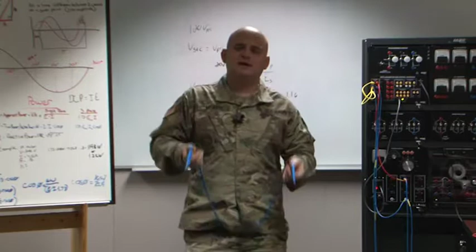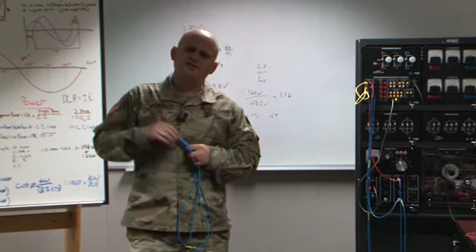For instance, if I have one transformer rated at 100 kVA, and I put it in parallel with another 100 kVA transformer, and another 100 kVA transformer, so three transformers all in parallel, all single-phase, what do I get capacity-wise? I get 300 kVA worth of power output. That's one of the principal things about transformers in parallel: you're increasing your power capability.